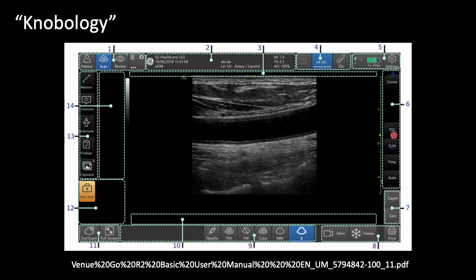Your time gain compensation, or TGC, you can adjust your gain generally by adjusting here or by using your gain setting, or you can change your time gain compensation. So this will change the gain based on which level you want to adjust. So you don't need a lot of gain up here close by because there's little impedance, there's little attenuation of your signal. But as you get down here, you may lose a lot of your signal, and so you want to add more gain to these further structures down here.